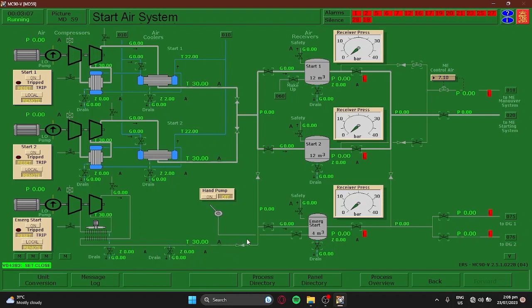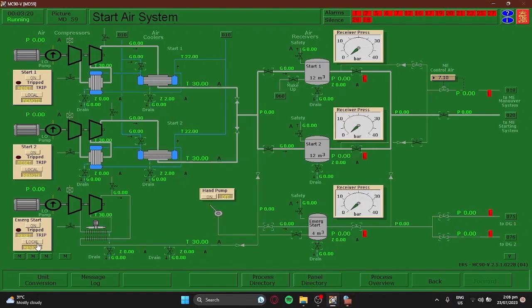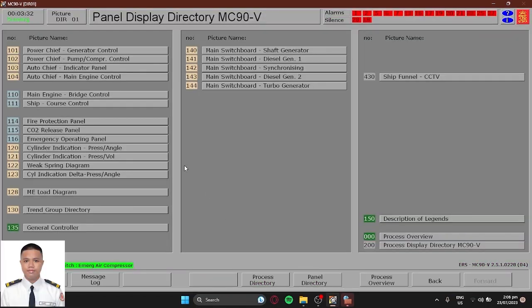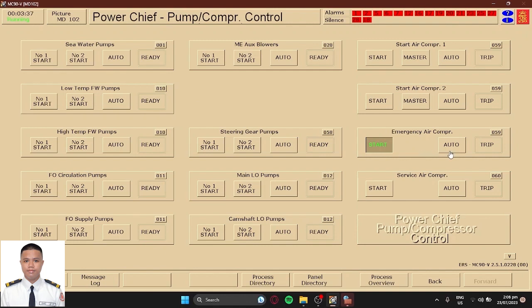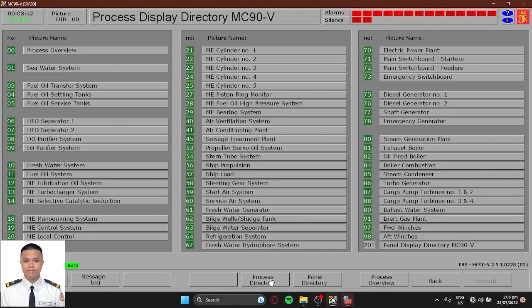Next step is to line up the valves here. Press this, open this up, open this, valves leading to DG1 and DG2. Next step is to turn this emergency air compressor start into local here. Turn this into local, then turn this on. Once it's turned on, set it back to remote. Go to panel directory, go to 102, pump and compressor control here. Then auto the emergency air compressor. Once that's done, go back to process directory.